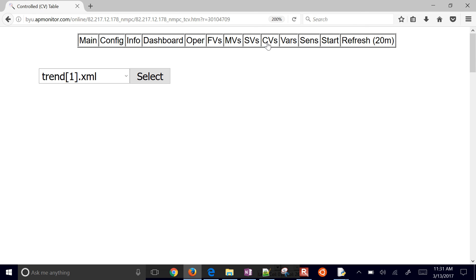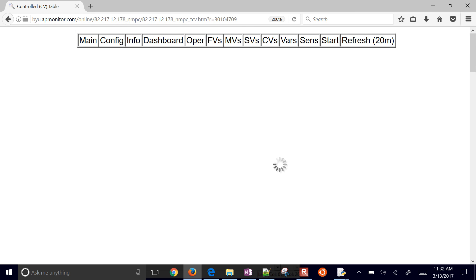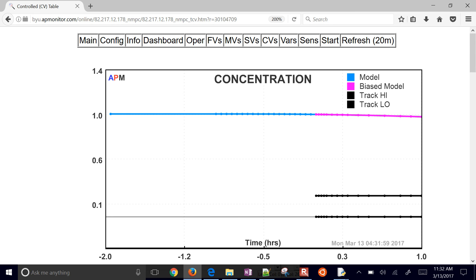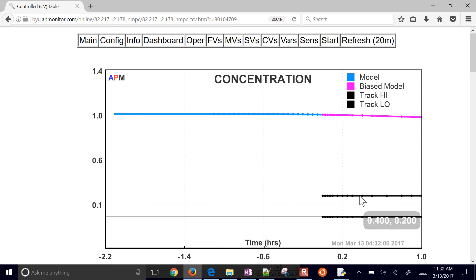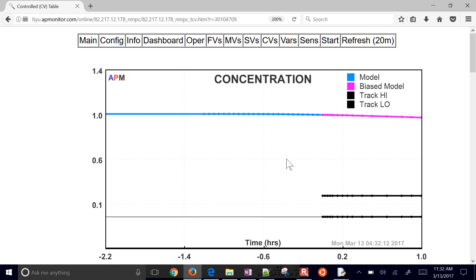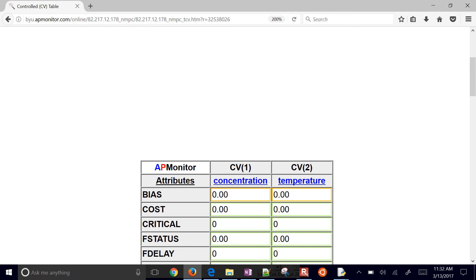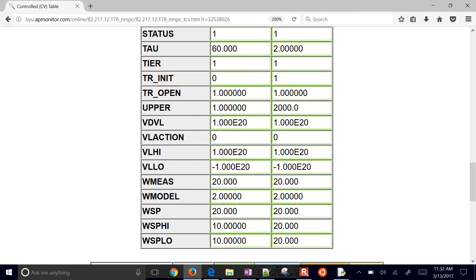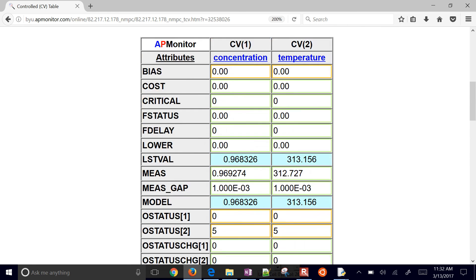If you go to CVs and select concentration, you can see the dead band — it's trying to control the concentration to between the upper limit of 0.2 and lower limit of 0.1. Right now the temperature is the higher priority. Looking at the weights table, temperature has a weight of 20 and concentration has a weight of 10 on the left side, so temperature is higher priority right now and we're going to be trying to track that.